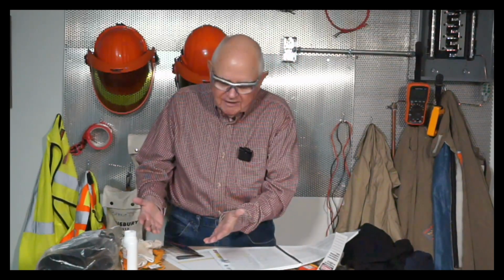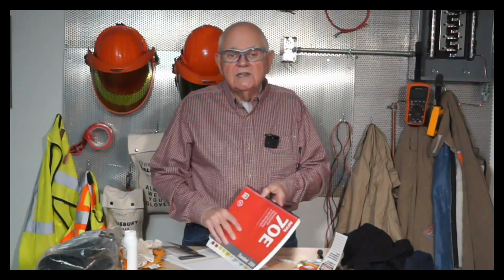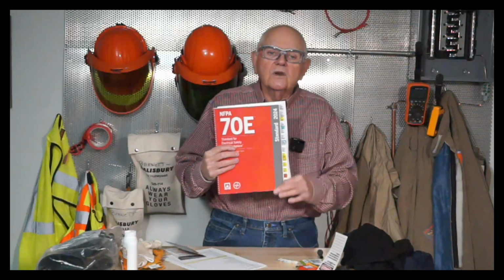So anyway, we comply with the 70E standard. We have a written electrical safety work program for our facilities. You're required to review your written electrical safety work program periodically. All the information is in 70E. Open up your 70E book to what's required in your electrical safe work program and compare that to your program, bounce them across one another, see if you need to make any improvements. As I say, as of this Tech Talk, we're using the 2024 NFPA 70E. So, we have to write a job safety plan. We have to have a documented job safety plan for the electrical work that we're going to do.